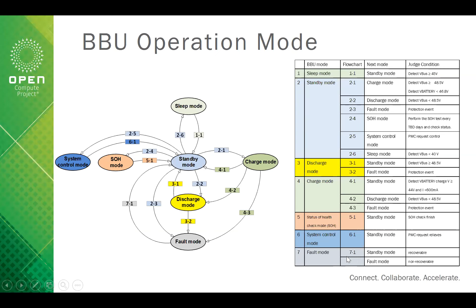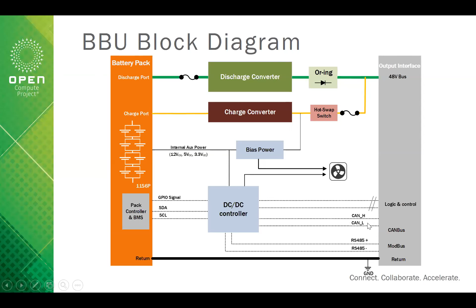This page is showing the block diagram for our BBU. We have the battery pack and the BMS function, which can provide each cell voltage and current to our DC-DC controller. We also have the discharge converter, which can regulate the output voltage from 48 to 47.5 volt, and the charge converter, which can charge the battery in constant current or constant voltage mode. Internally, we also have the bias power for the housekeeping and for the fan. The DC-DC controller gets the information from the battery pack and provides communication to the system, using RS-485 Modbus and also the CAN bus for BBU to BBU communication.